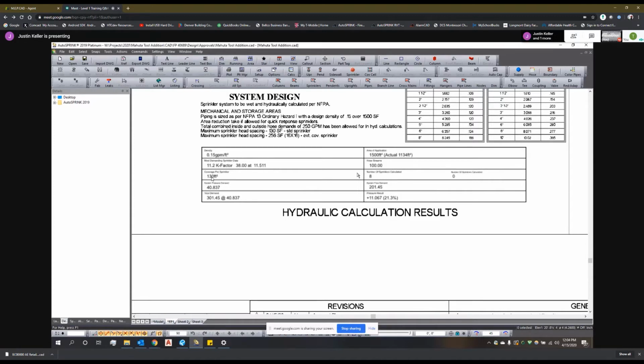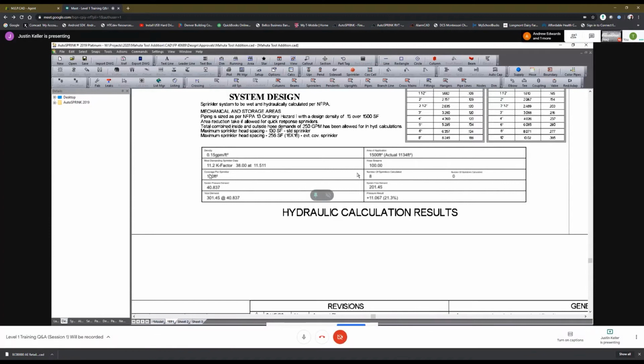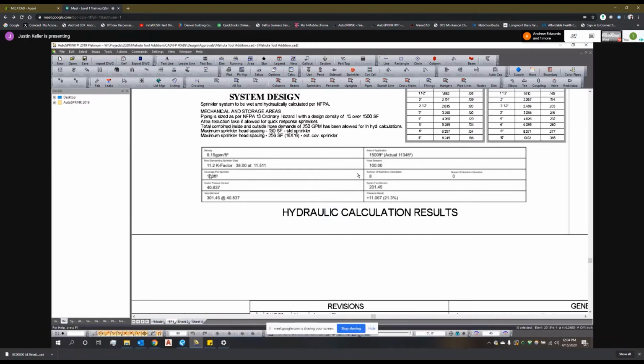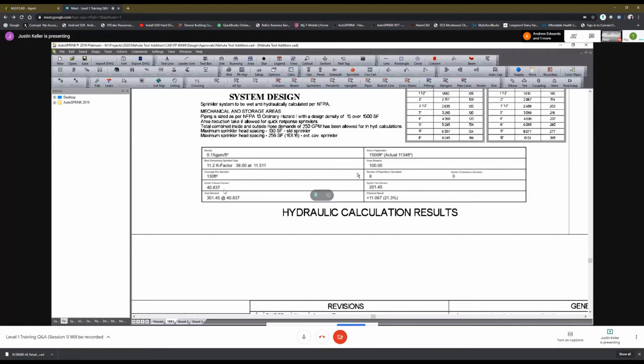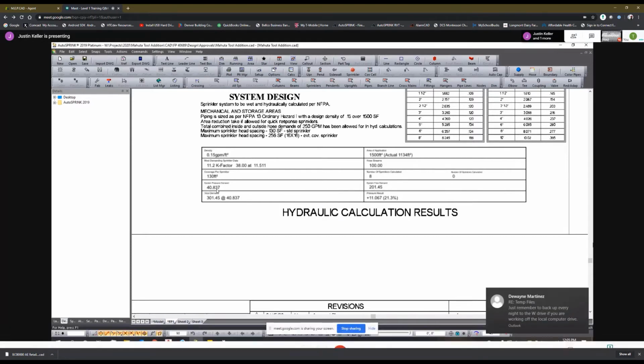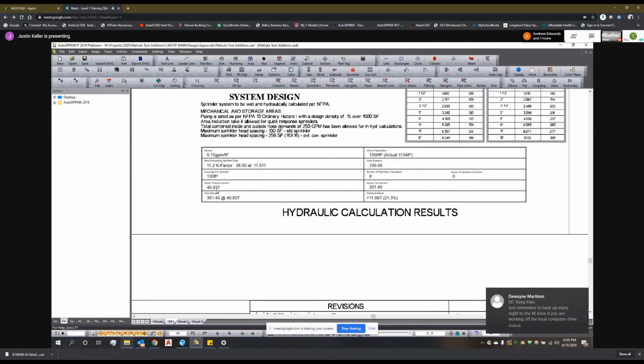The riser tag, I think it might, but it's going to pull that information from the spacing values that you establish in your remote area properties, not specifically the coverage that you might establish in the properties of your sprinklers. But it certainly will populate the pressure demand, both total pressure demand at your water source as well as pressure demand at a base of riser if you've placed a checkpoint gauge.